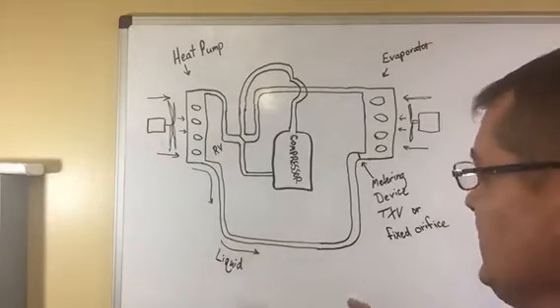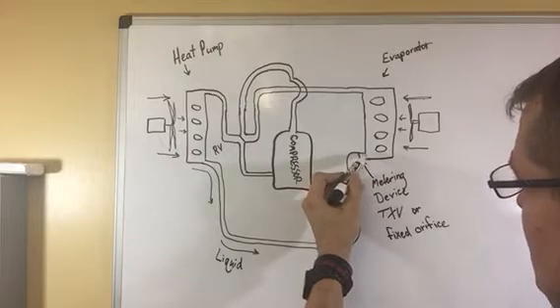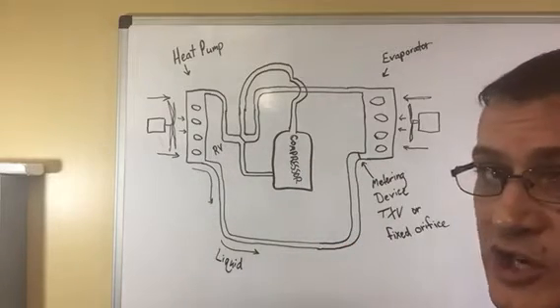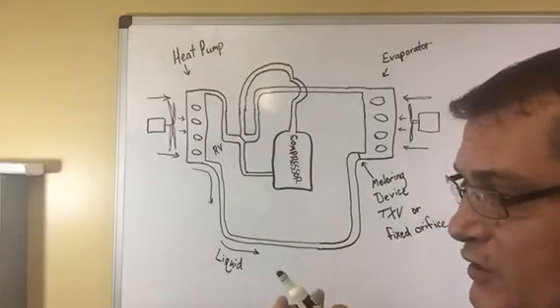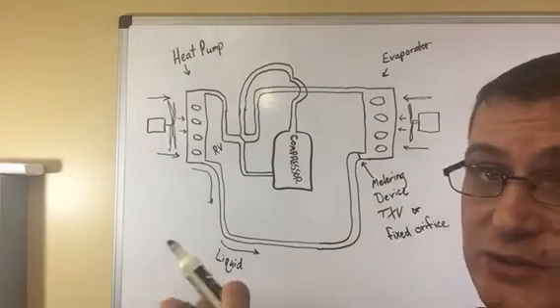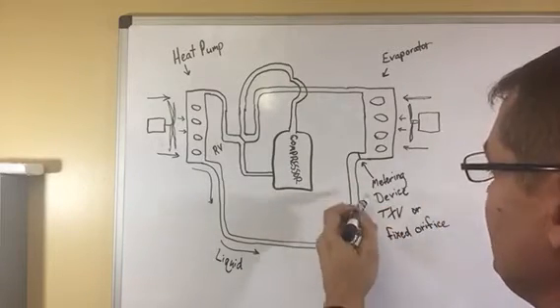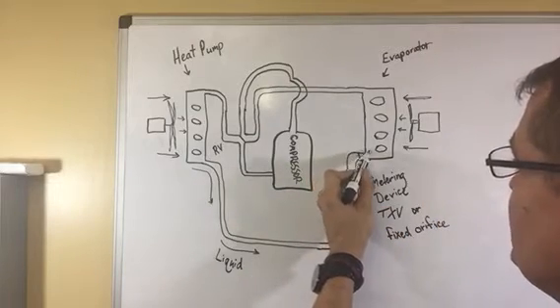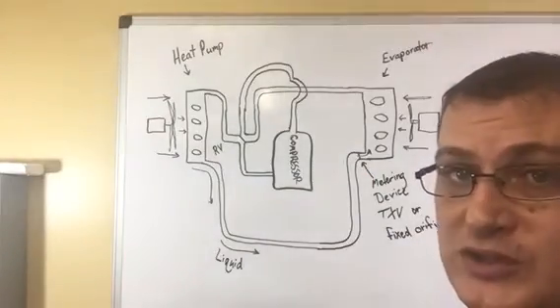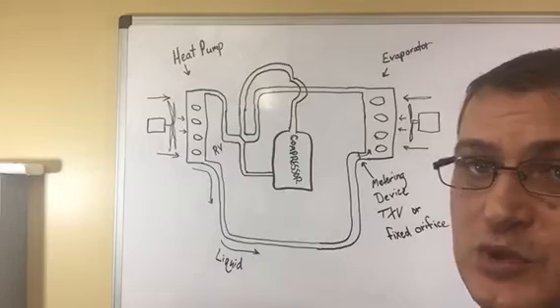There's a metering device at the evaporator coil. That causes a decrease in pressure because the liquid refrigerant has to squeeze through this little bitty hole, whether it be the expansion valve or the fixed orifice. So as the refrigerant sprays into the evaporator coil, it sprays and boils. And as it's boiling, it absorbs the heat from the air that's being passed over that coil.